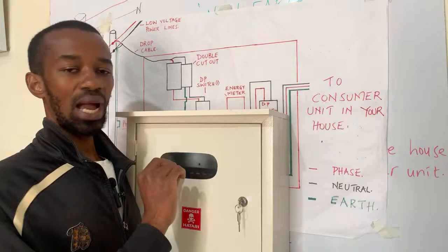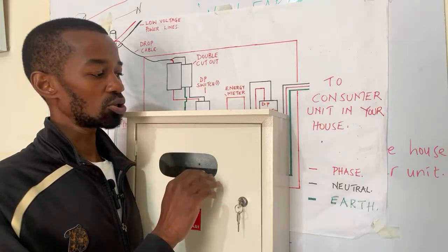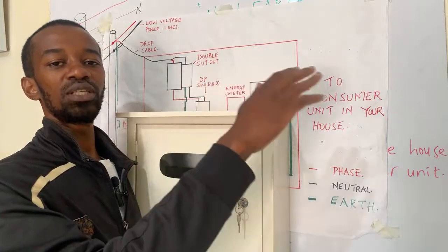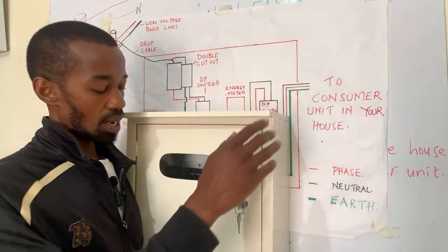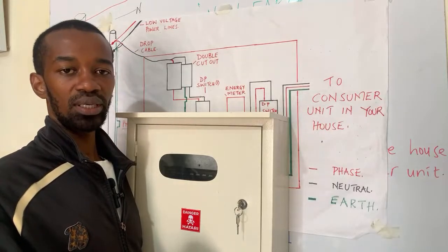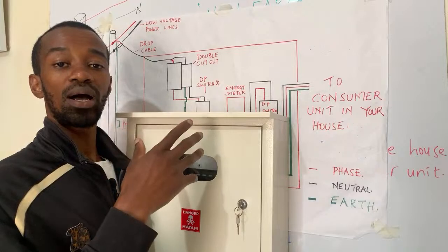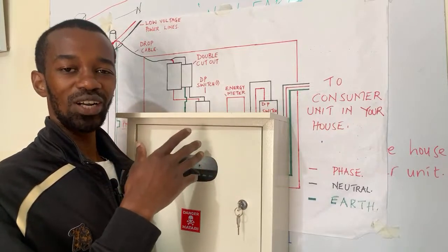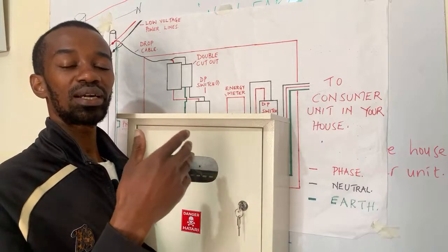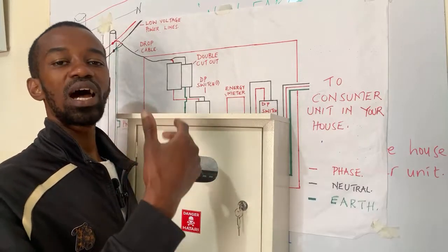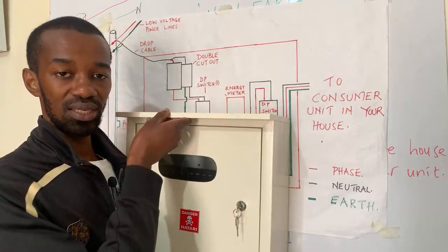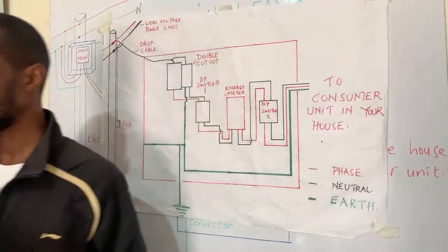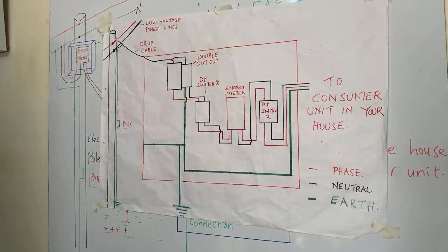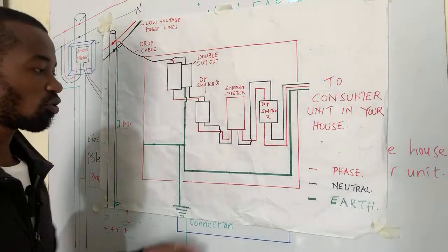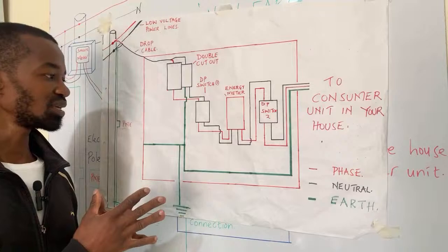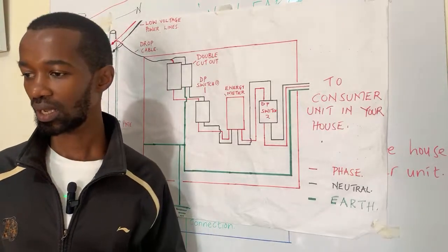The reason I would prefer several earthing points is because if, for instance, you're talking about a 20 or 30 feet structure, and you have earthed at the meter box only, and this structure is not made of copper, meaning it's not a good conductor of electricity, you definitely cannot rely on one earthing point. You can even have four or more, so that the earthing connection is done in a manner that is safe for the occupants, or very safe for the people undertaking a business activity in that setup.